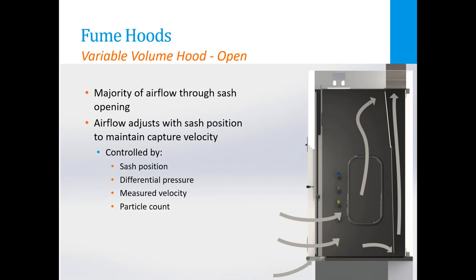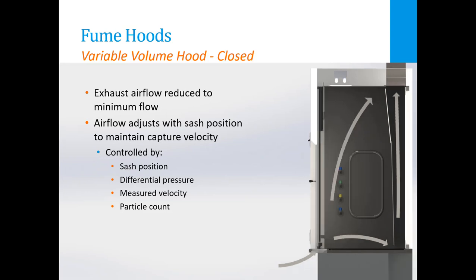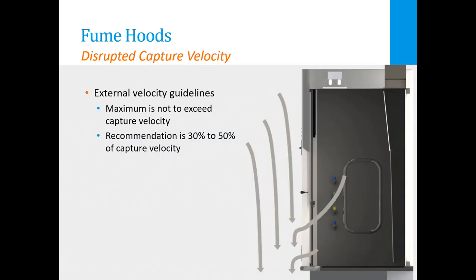The change in volume can be controlled by a number of different methods, including sash position, differential pressure, measured velocity, or even particle counts within the hood. In the closed position, the hood operates at a minimum flow rate to maintain negative pressurization within the hood at a set level. With either type of hood, it's crucial to maintain velocity through the face of the hood. This ensures proper operation and containment of contaminants.